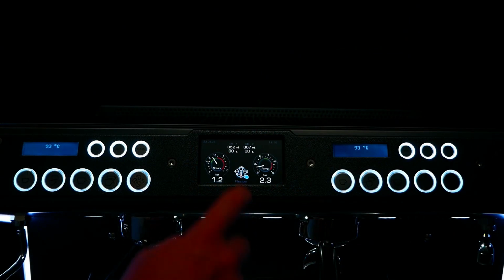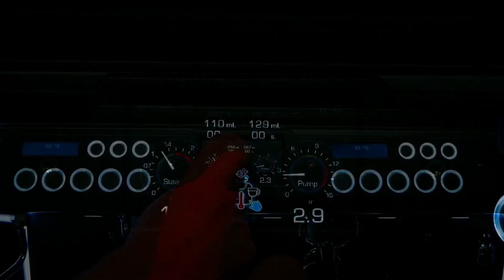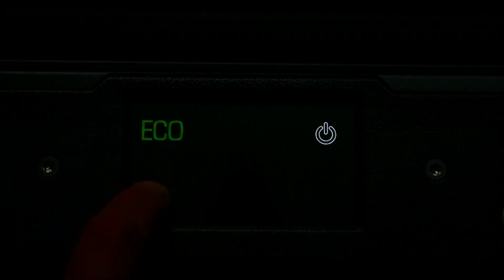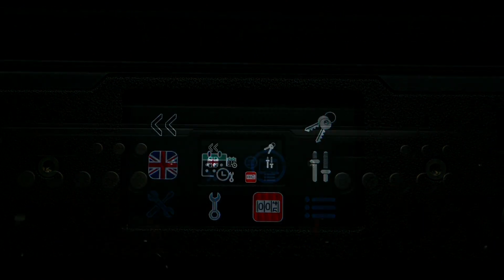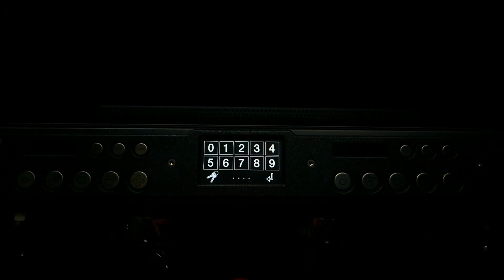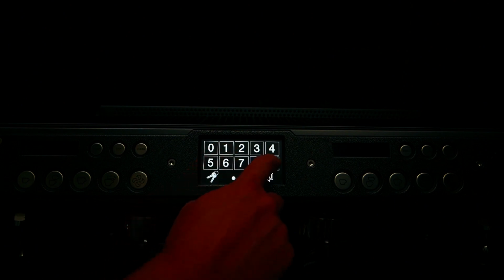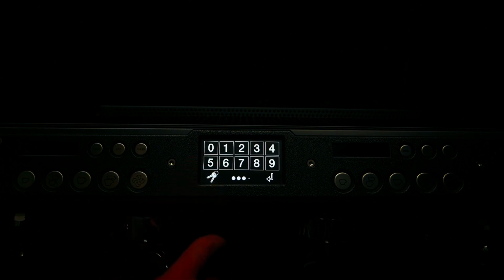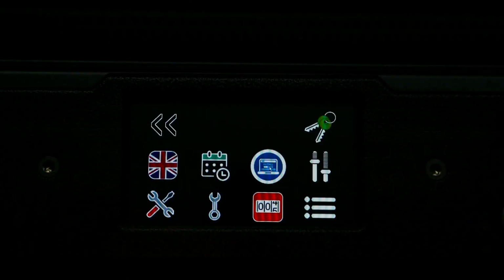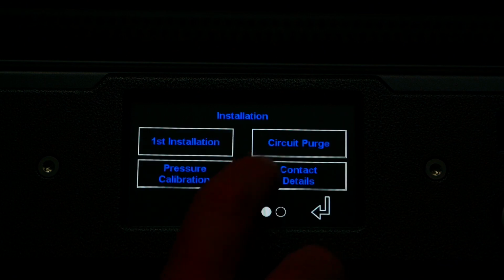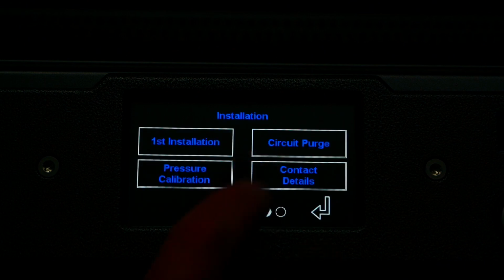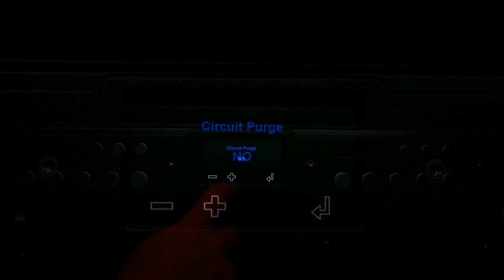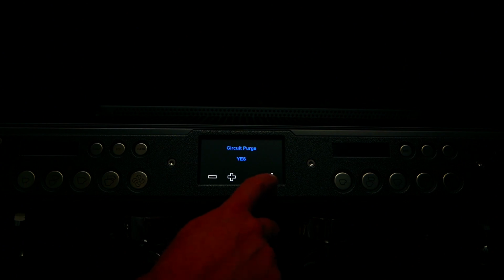Following the same process as the first install, enter standby mode and access the technical menu. Then select the icon with the key and use the password 1956. Select the installation icon again and this time select the circuit purge program. Use the plus key to scroll to yes and the tick key to activate the program. If your workspace is quiet, you will hear air being evacuated down the waste as the air escapes through the purge valves.